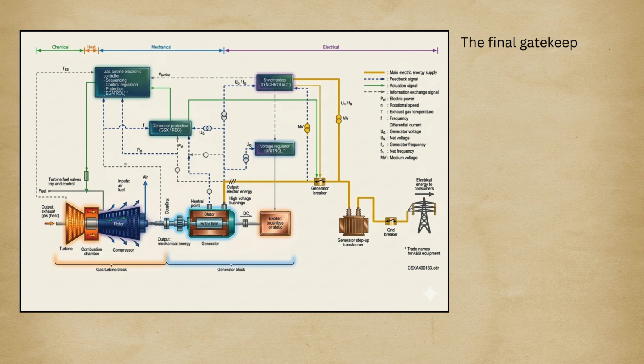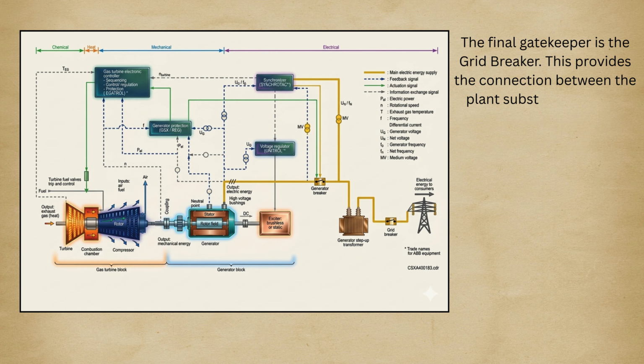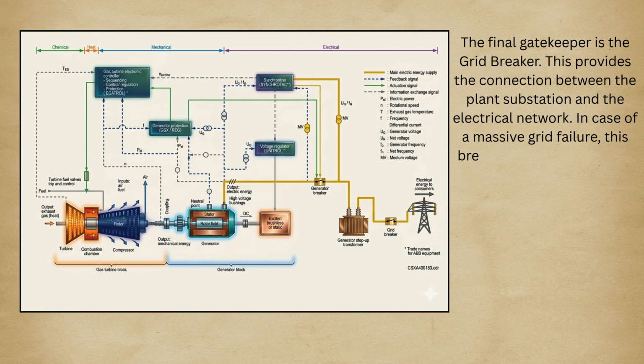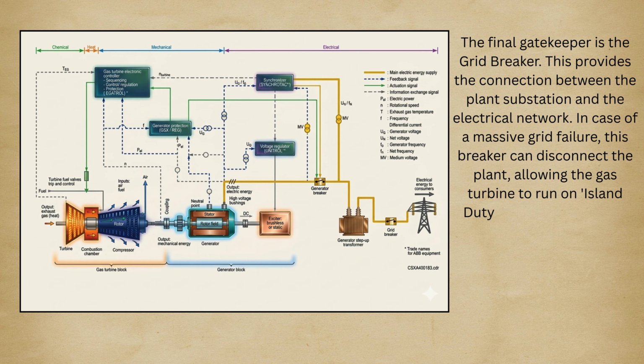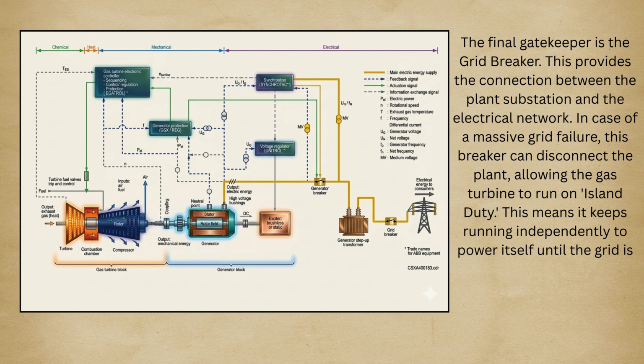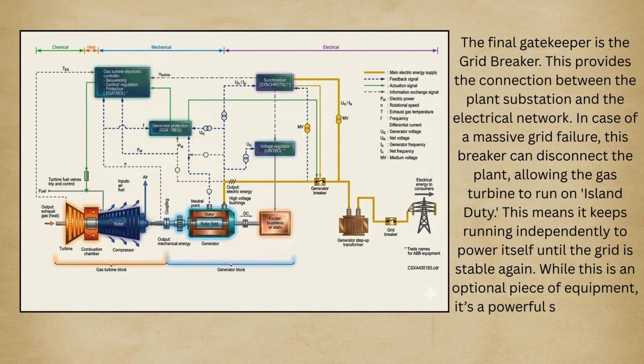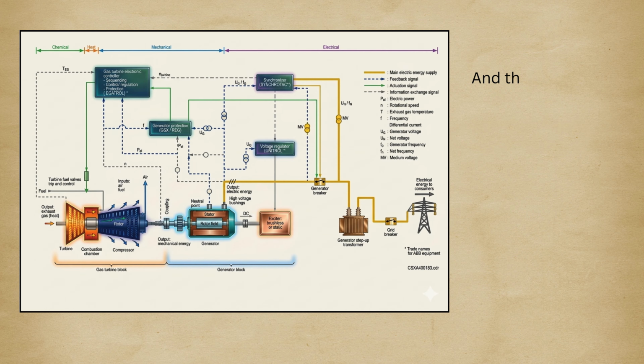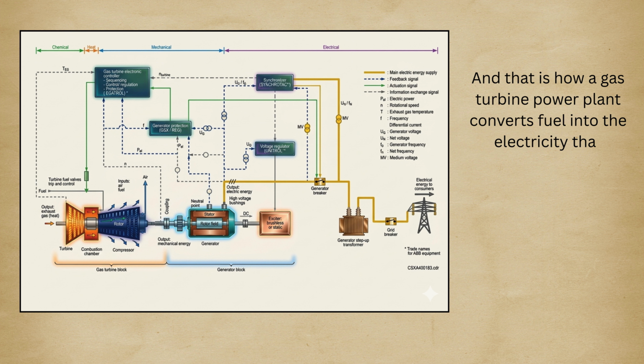The final gatekeeper is the grid breaker. This provides the connection between the plant substation and the electrical network. In case of a massive grid failure, this breaker can disconnect the plant, allowing the gas turbine to run on island duty. This means it keeps running independently to power itself until the grid is stable again. While this is an optional piece of equipment, it's a powerful safety net for the system. And that is how a gas turbine power plant converts fuel into the electricity that powers our lives.